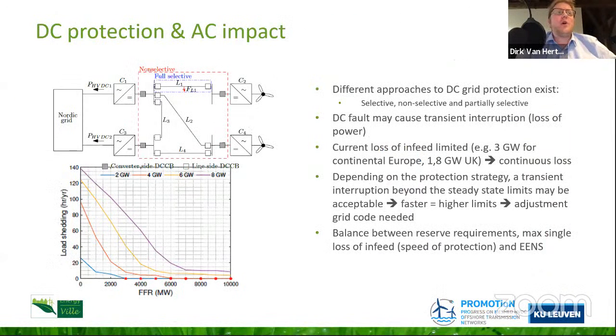Looking at what is going to happen, I'll be quick. If you have such a big DC grid, faults will happen occasionally, and depending on how you protect the system, they will have a different impact on the connected AC system. Will you affect a single converter or multiple converters at the same time? This depends on how many breakers you need to buy and how expensive your system will be. But it will also mean the expected amount of lost power will change, so you need to think about the reserves in your system.